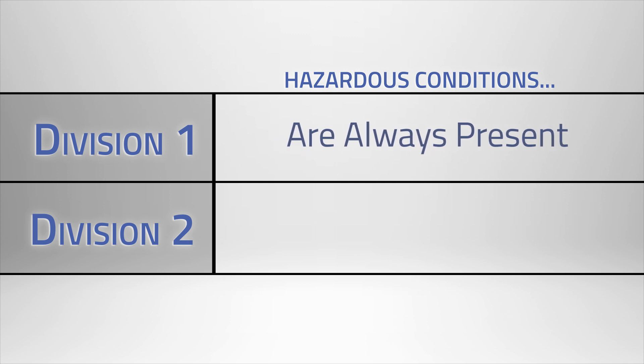Under a class there are also two divisions. In Division 1 environments, hazardous conditions are always present. And in Division 2 environments, hazardous conditions may be present.